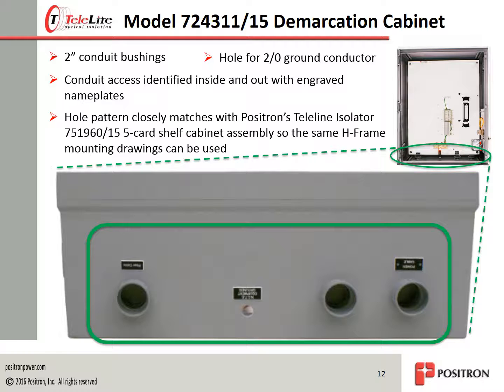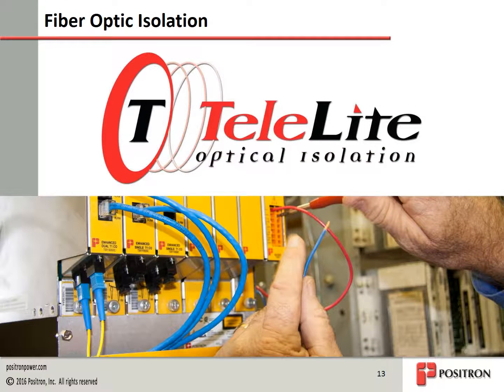Designed for reliability in the harshest of electrical environments, for more than a decade, Positron's TeleLite optical isolator has served in substations in all corners of North America. Designed and manufactured to the latest standards in surface mount technology, TeleLite has been tested and certified to NEBS Level 3, which is the most stringent standard for telecommunications equipment today. TeleLite offers you a mature solution to continue a dielectric fiber entrance feed to the control house on the power utility side of the DMARC point.